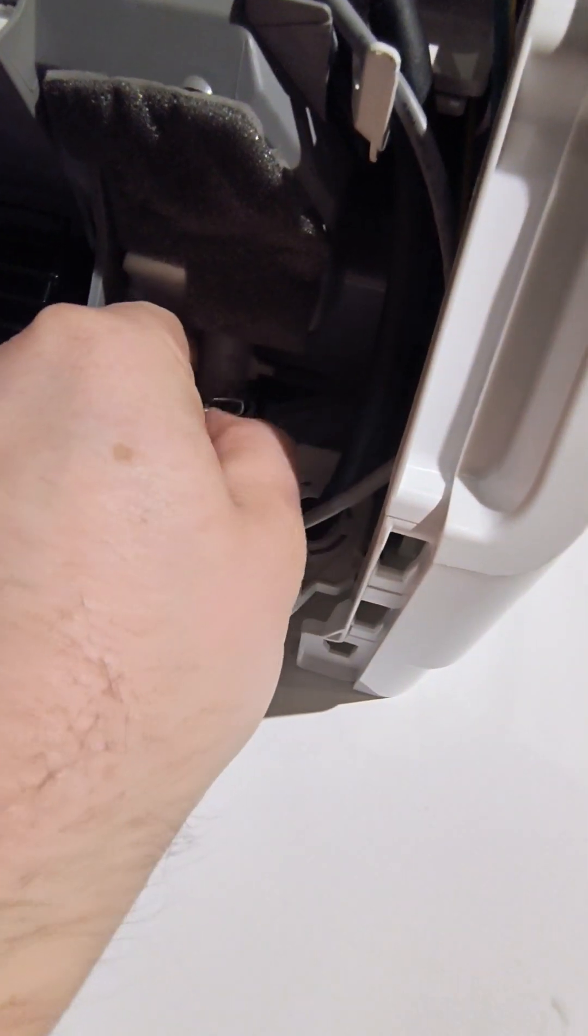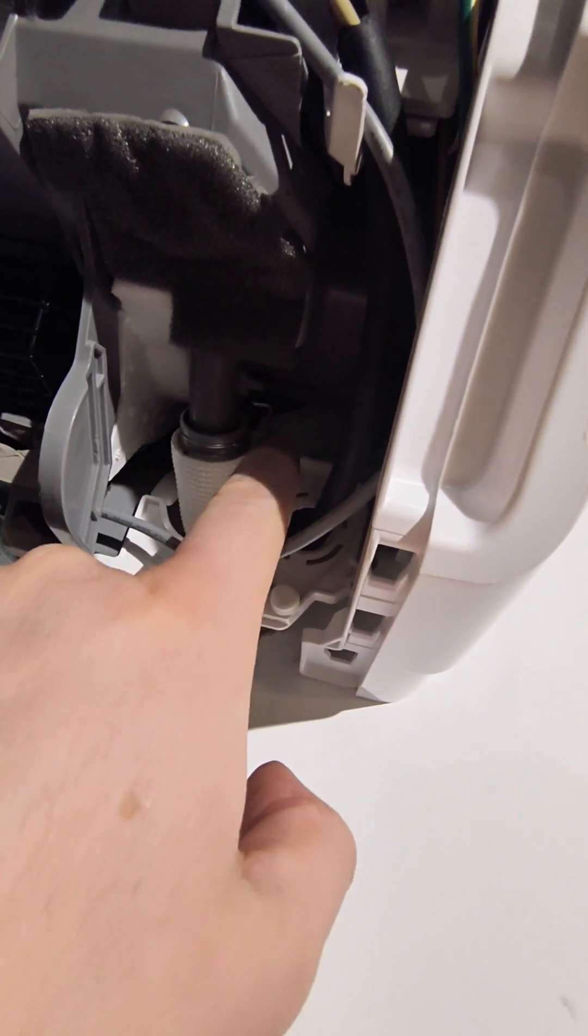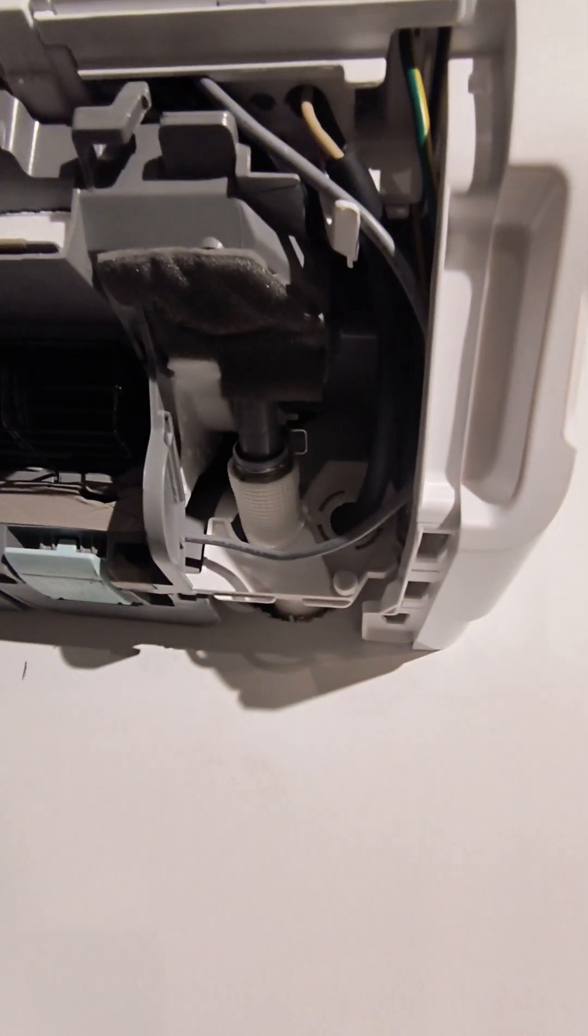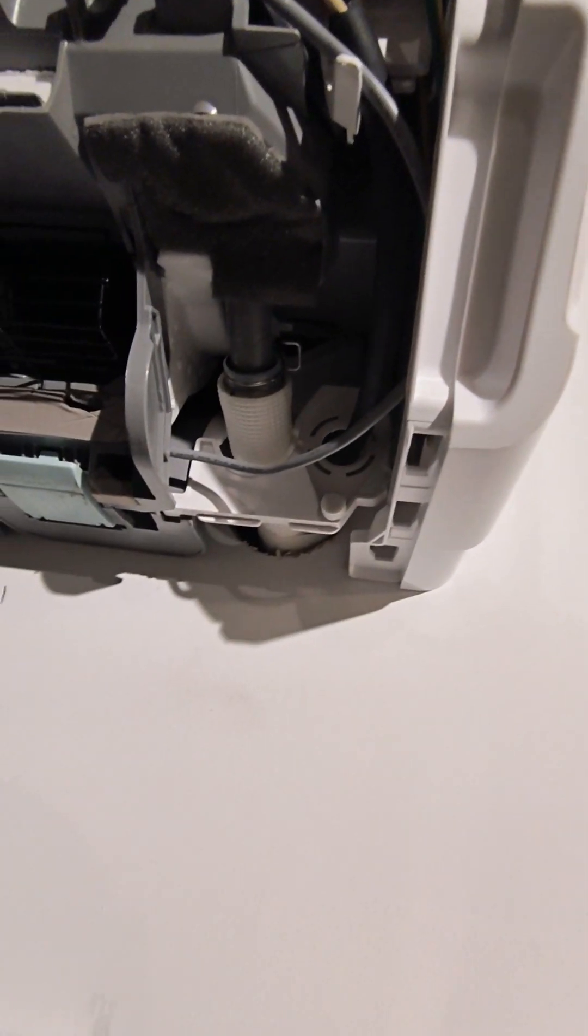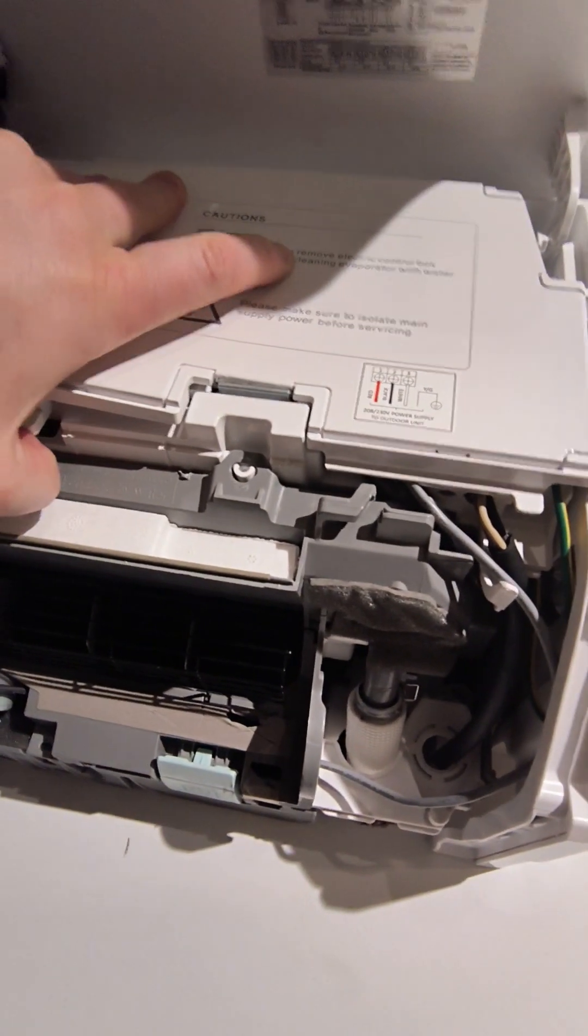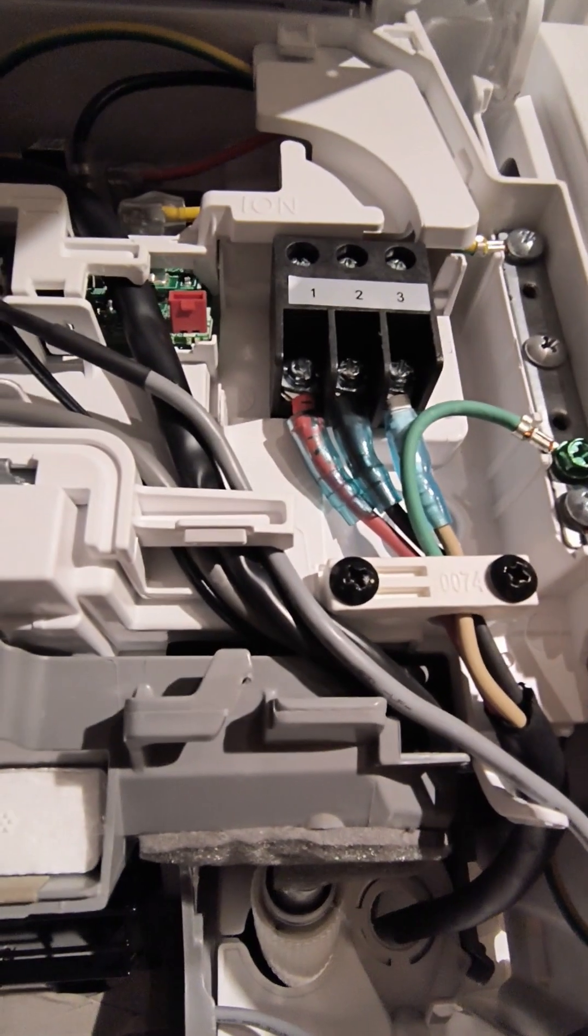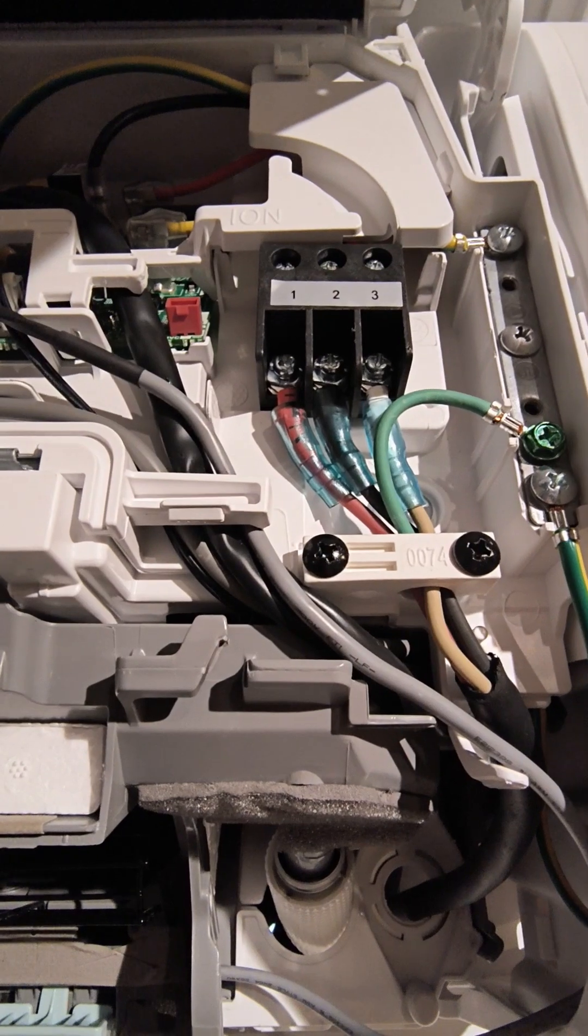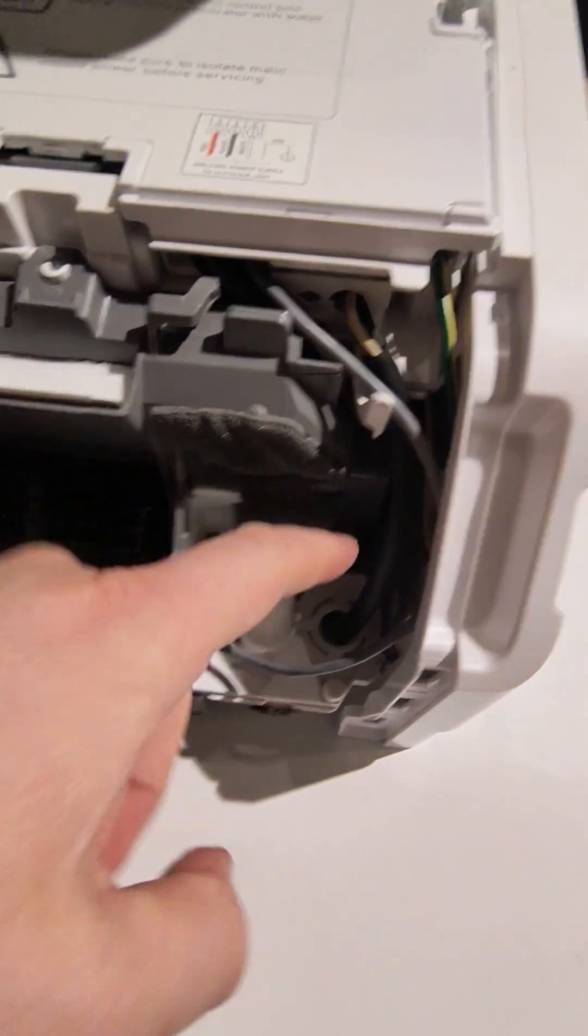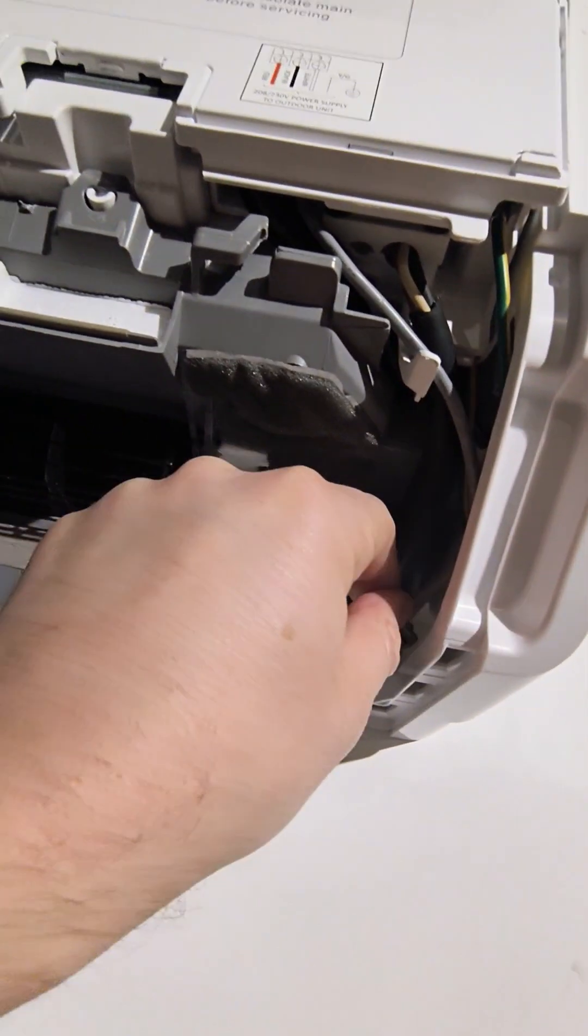You take a little screwdriver or needle nose pliers - that's supposed to be locked up into here. If you do have a unit that's not draining properly, that's where you would pop the hose off and blast it with air or something else. Again, don't poke around with this unless you're comfortable and you have the power secured. That's where the communication wire comes in. You can check voltages here and do some basic troubleshooting. Communication wire also goes out with the copper line set and the drain.